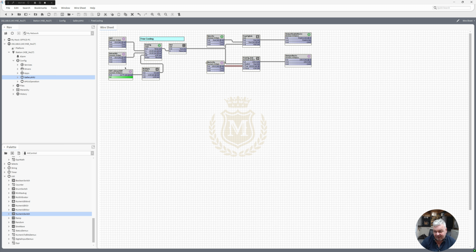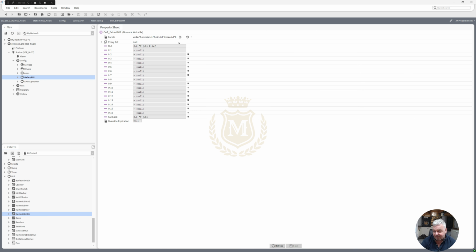And in case you wanted to make sure that they can't use anything less than that, you would set that minimum there to 2. And then that way they can't go lower than 2. So if you try and set that lower than 2 and set it to a 1, it won't let you. It's giving you the 2 to 4 setting there. It's got to stay at a 2. But I could put it to a 3, or I could put it to a 4.